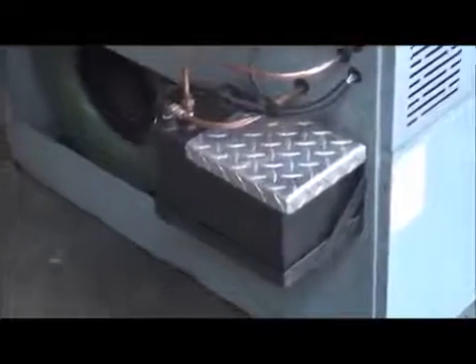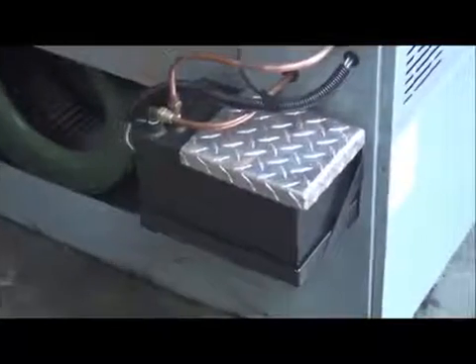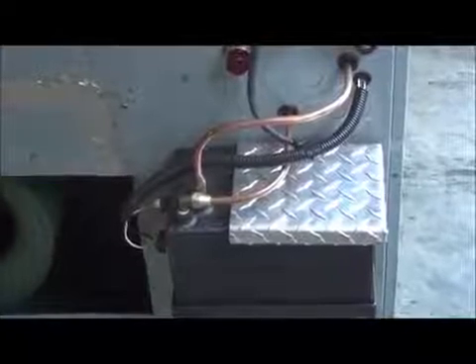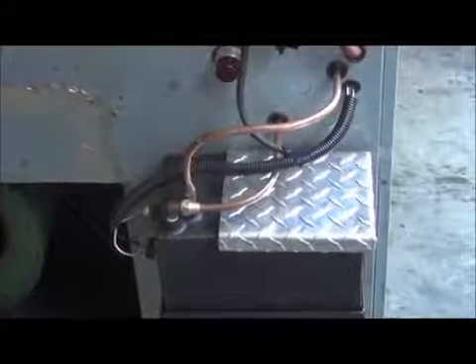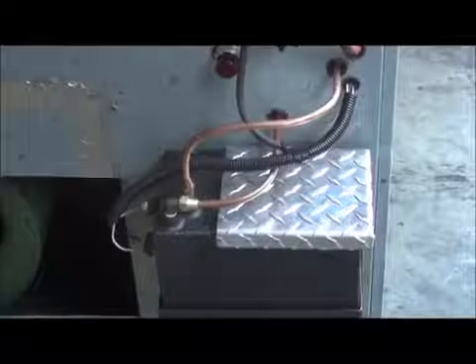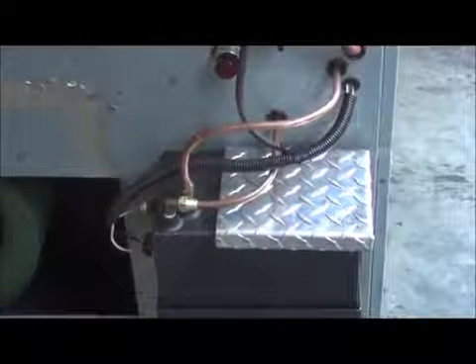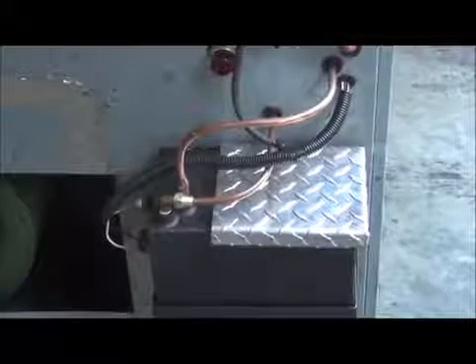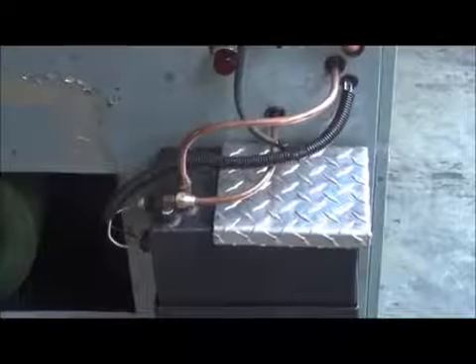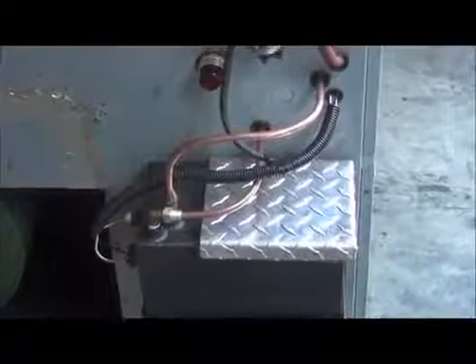And right here we have our oil siphon tank. It's a small tank that's attached right to the side of the furnace here. And it's heated with a small 110 volt heating element that's commonly used in RV hot water heaters. And we have our suction and return lines here. I use the existing oil pump in the burner to continuously circulate oil through this. And what that does is it makes sure that the oil is evenly heated, so we're not sucking up any cold oil into the nozzle. And that's an upgrade from my old furnace.